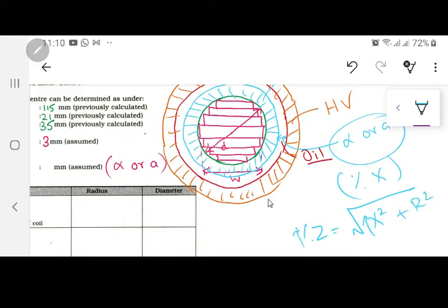So you are actually increasing what? You are increasing jXP or jXS of your transformer. In the equivalent circuit with RS and RP, you have jXP and jXS, so you are increasing those leakage reactances. But on the other hand, you have an advantage also. You are making the inside winding, which is certainly the low voltage winding, cool down better.